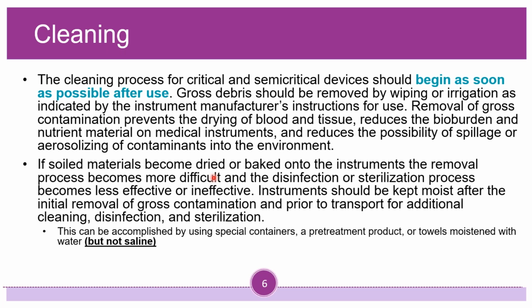That's a problem, because when it gets back to SPD, they're going to have to make sure that that instrument gets cleaned, and it makes their job way more difficult, and it's not a best practice. So soiled materials need to remain moist. This can be accomplished by using special containers, a pre-treatment product, or towels moistened with water. So why can we use sterile water but not saline on our instruments? What's the limitation with saline?